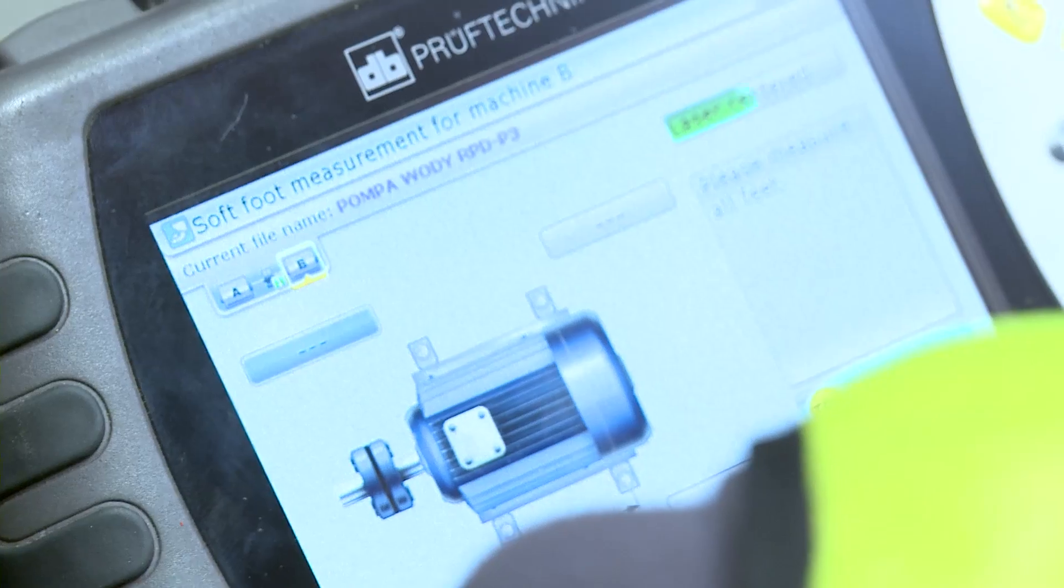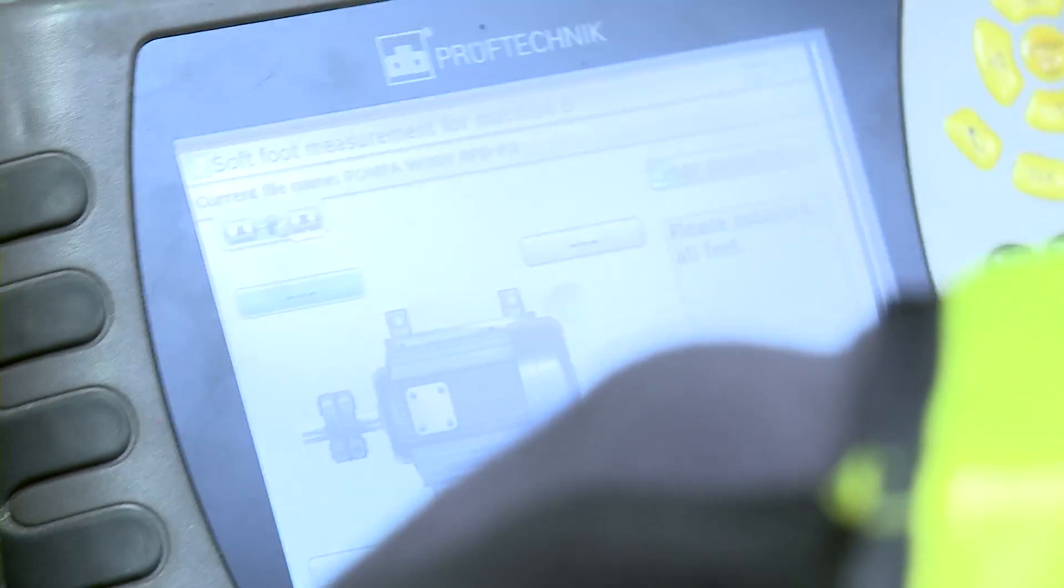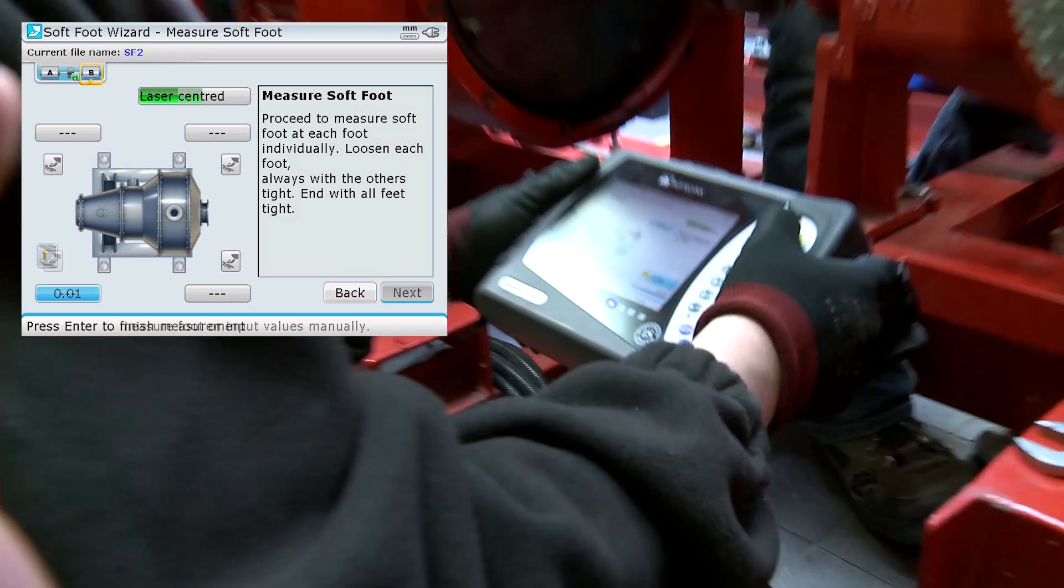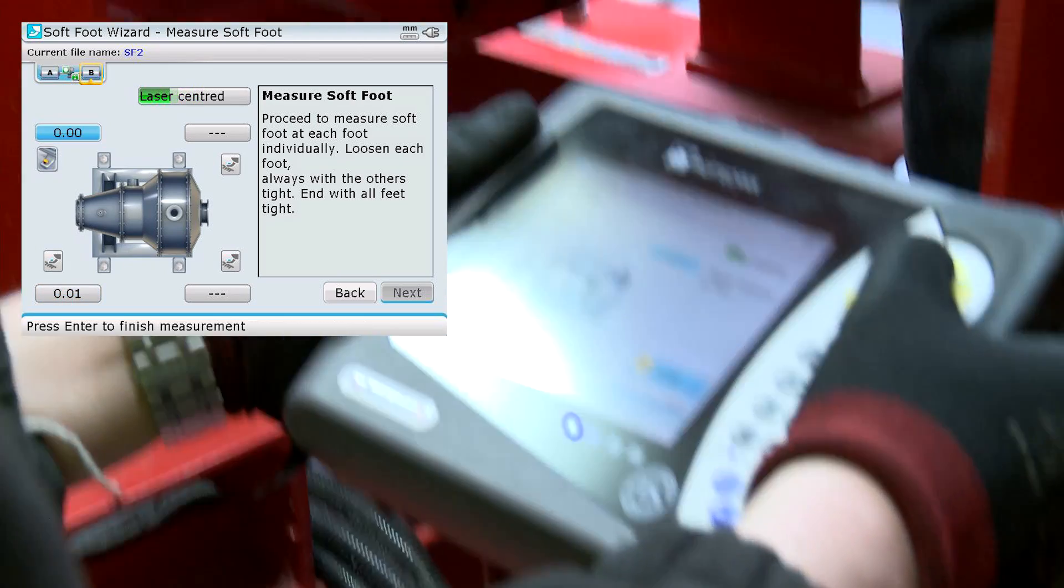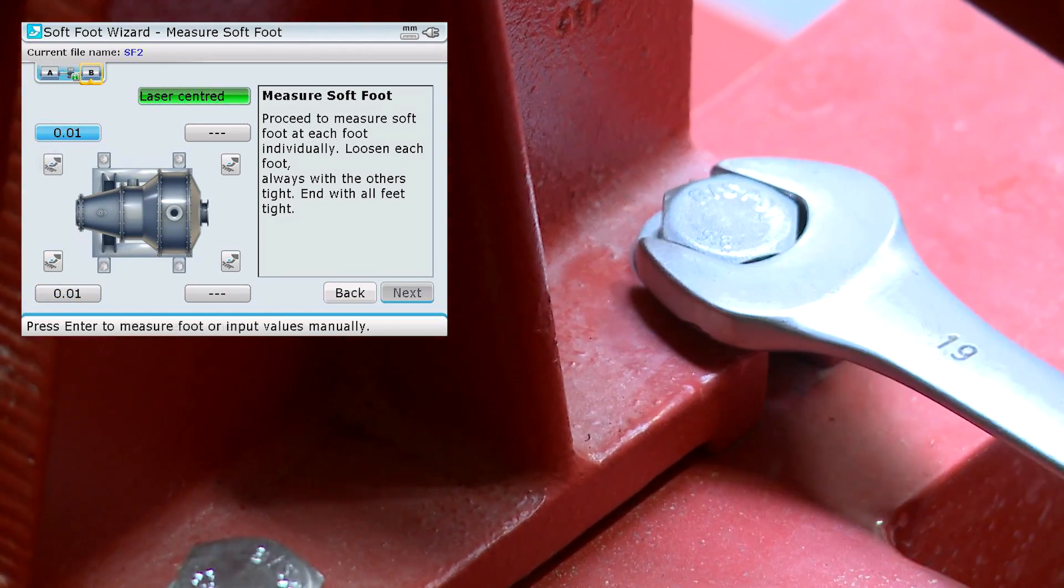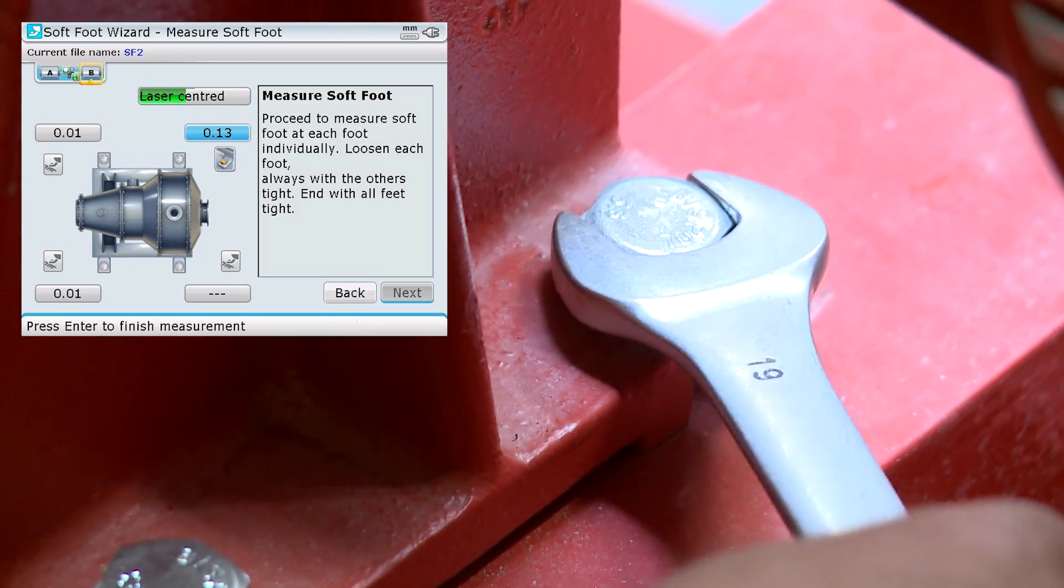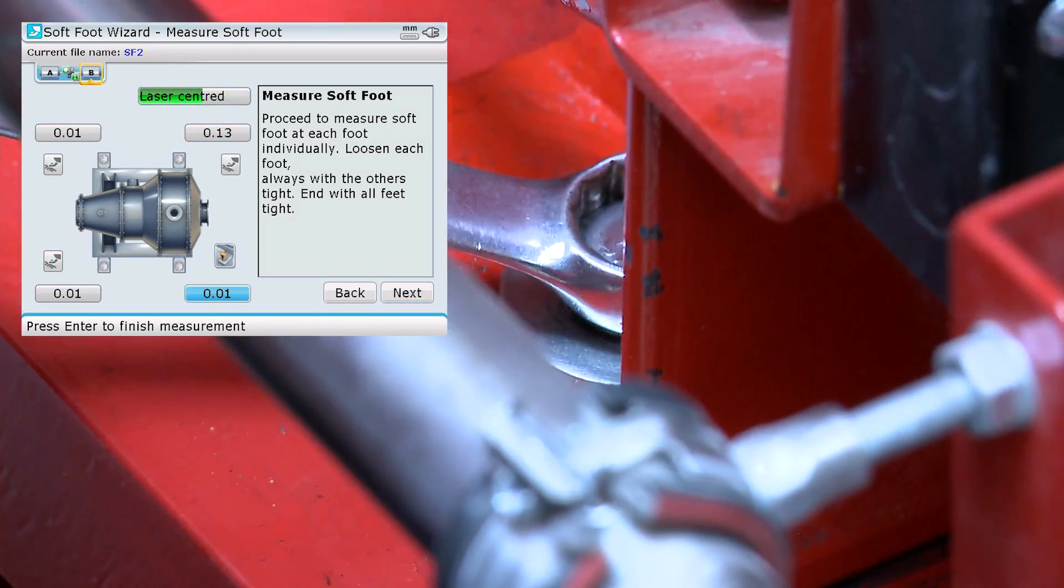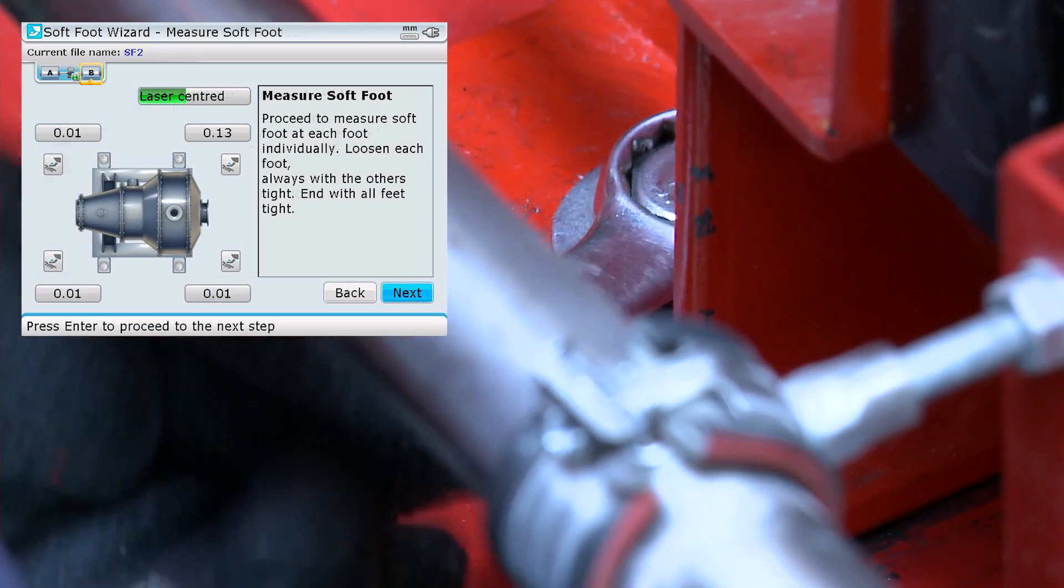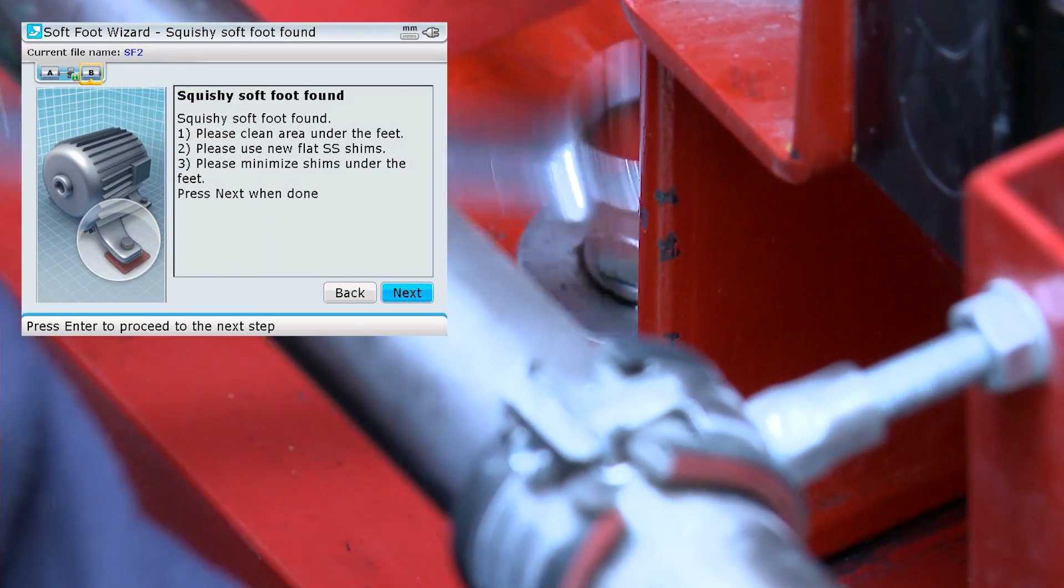The Rotalign wizard considers differences in shaft deflection as bolts are loosened or tightened. As Greg tightens each bolt, the wizard reports the shaft alignment conditions in real time. Today the wizard has detected a squishy soft foot problem.